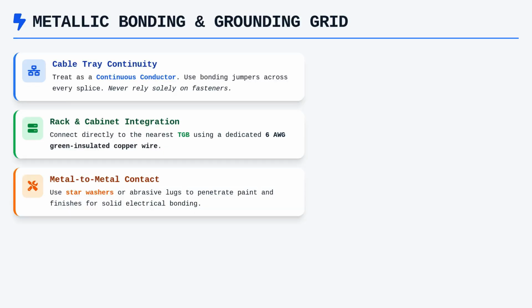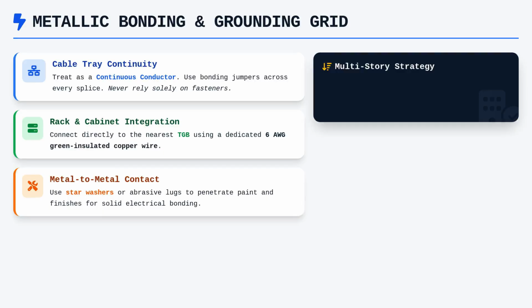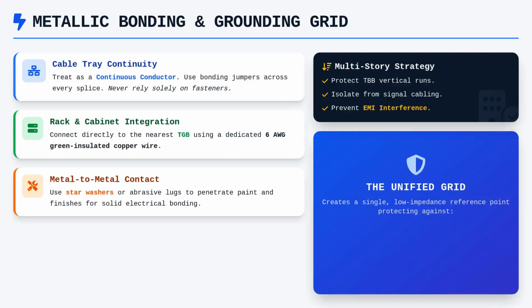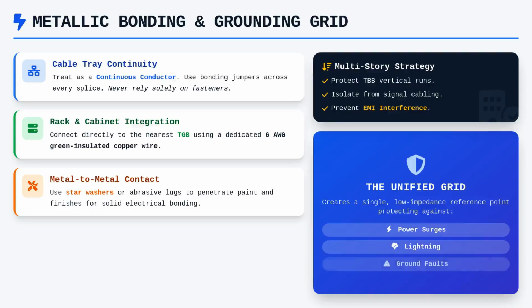All attachments must use identified hardware, such as star washers or abrasive lug connections that penetrate paint and finishes to achieve solid metal-to-metal contact. If you are dealing with a multi-story building, the vertical runs of the TBB must be protected and properly supported within the telecommunications pathways, taking care to isolate them from signal-carrying cabling whenever feasible to prevent electromagnetic interference. This holistic approach creates a unified, low-impedance bonding grid that serves as the single reference point for the entire installation. By strictly following these parameters, you ensure that the structured cabling system remains protected against power surges, lightning, and equipment-level ground faults.